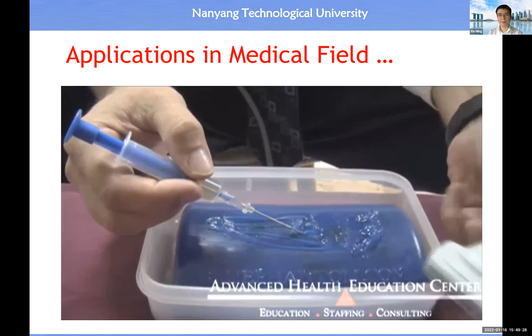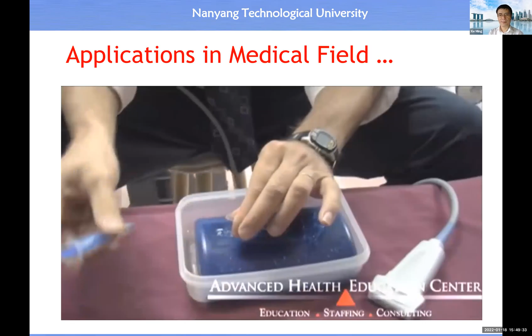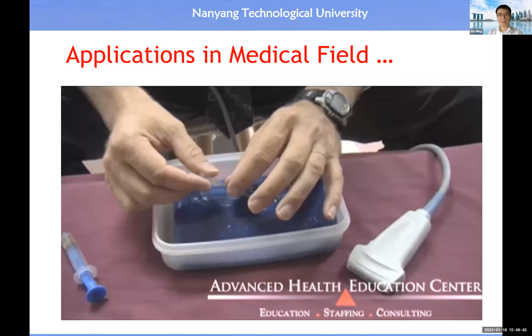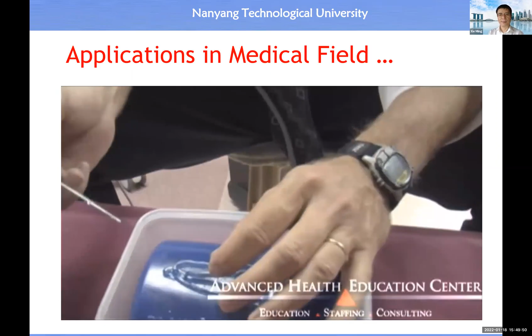We're now in the vessel. At that point in time, I can put the transducer down and disconnect the syringe. You can do this without a syringe. You can look for your blood flash right here. I can thread my wire if I'm going to do a PICC line. If I'm going to be doing a venous ablation, I can get my guide wire in. Once the guide wire is in, pull the needle out, hold your guide wire, and put in your introducer sheath right along the same pathway, and you've got instant access.